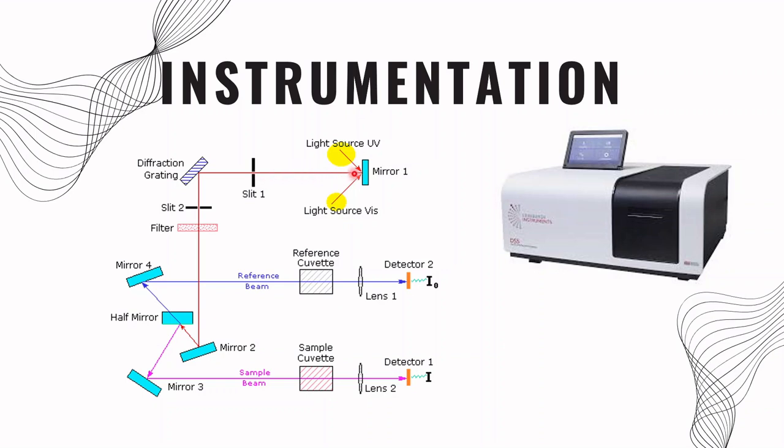Nowadays, most of the spectrometers used are double beam instruments. The light source is divided into two beams of equal intensity. These beams are passed through the sample and the reference. Normally, solvent is taken in the reference to nullify the absorbance due to the solvent. It's also needed to generate light of increasing wavelength, which is done by passing it through a rotating prism.